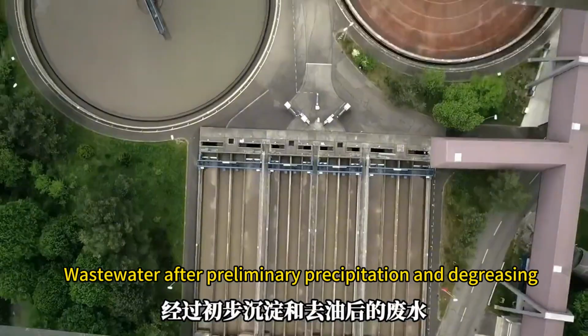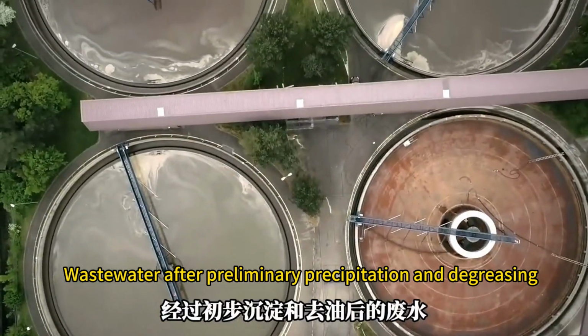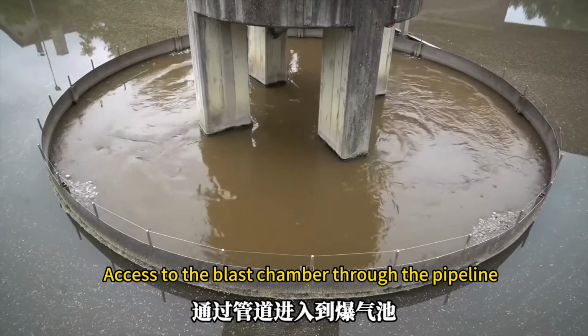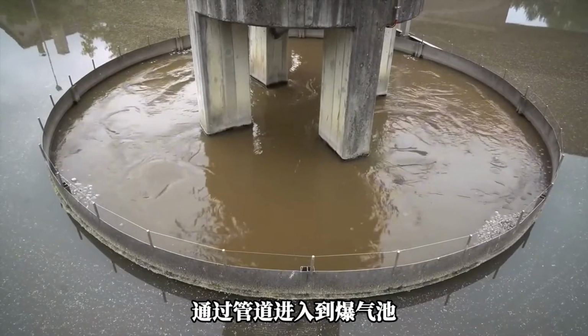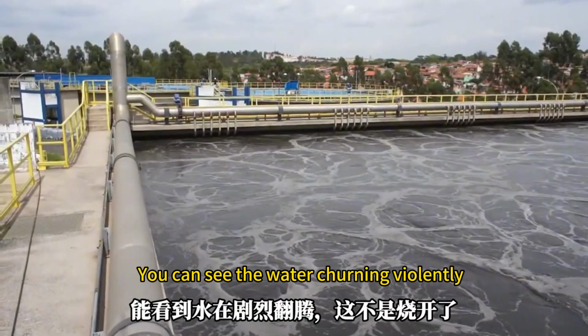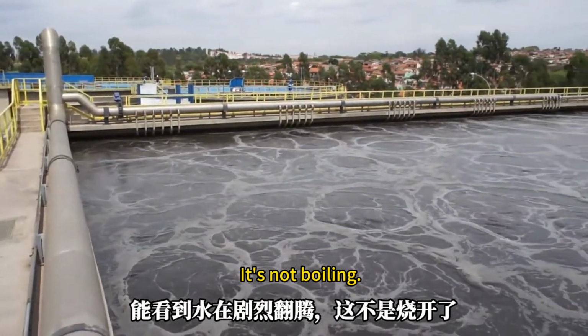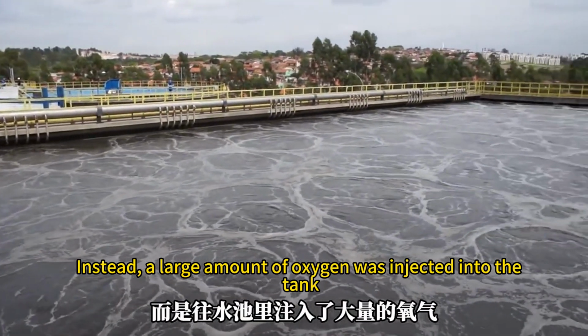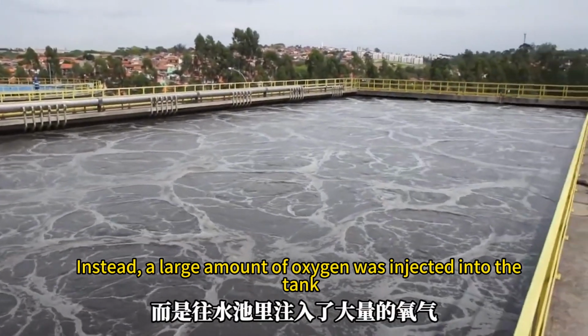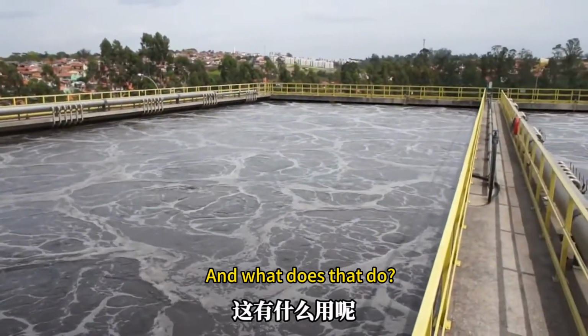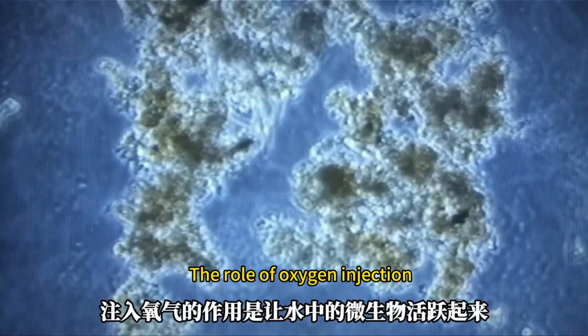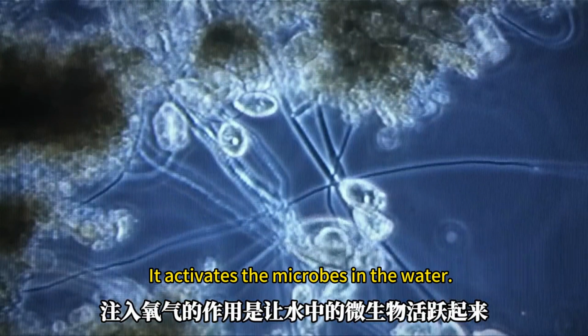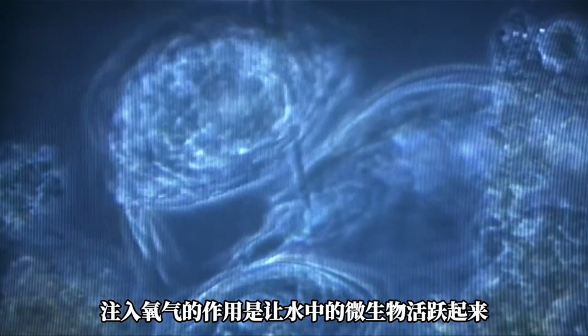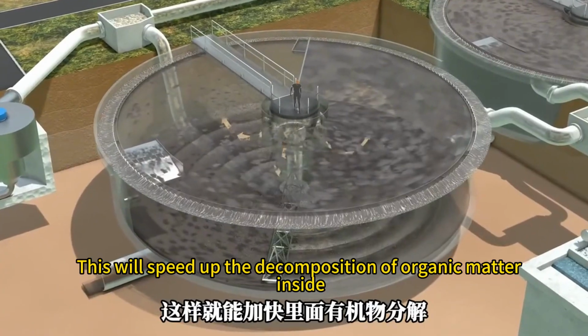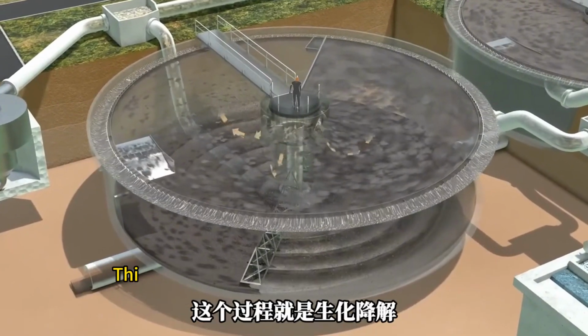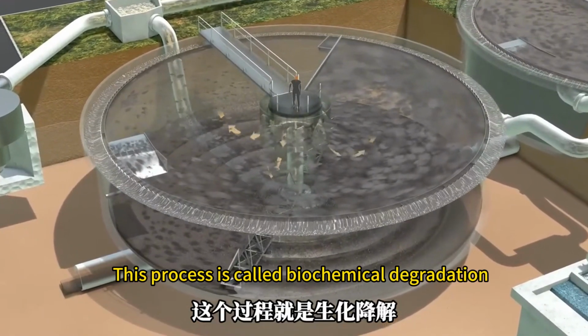Wastewater after preliminary precipitation and degreasing goes through the pipeline into the blast chamber. You can see the water churning violently. It's not boiling. Instead, a large amount of oxygen was injected into the tank. And what does that do? The role of oxygen injection is to activate the microbes in the water. This will speed up the decomposition of organic matter inside. This process is called biochemical degradation.